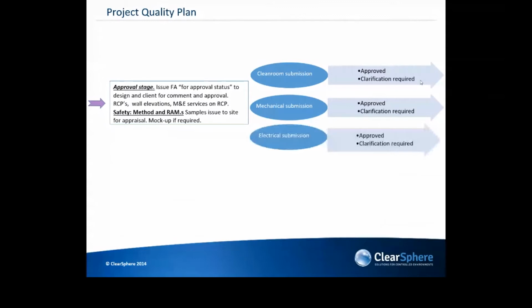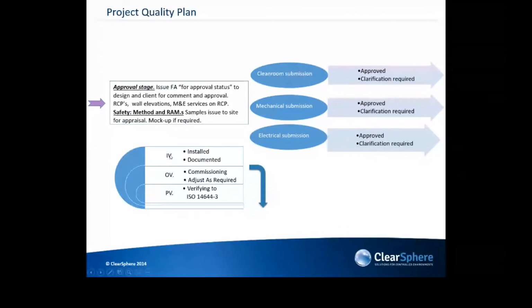Once all that is done, the install happens. So you have the installation verification, the installed material, and it's documented. We generate protocols for installation verification, operational verification, and performance verification. You go from installed and documented, moving on once that's signed off to operational verification for the commissioning of the HVAC system.